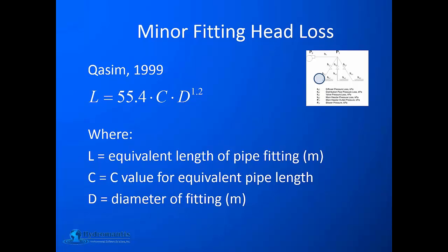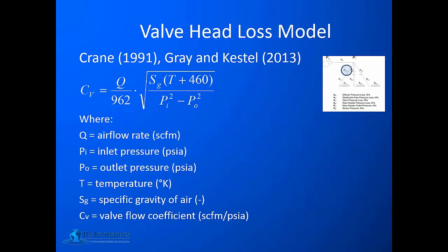To model minor fitting head losses, users can specify the equivalent length of fittings directly into the model, after which the pipe head loss equation is applied. For the valve head loss model, we use the equation proposed by Crane 1991 and also used by Gray and Kestel in their 2013 paper. This equation is based on a valve discharge coefficient linked to the air flow rate, specific gravity of the air, air temperature, and the inlet and outlet pressures.